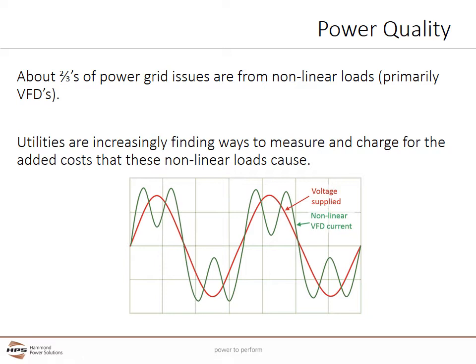Other large non-linear loads can include inductive heaters, arc furnaces, welders, and large DC power supplies and chargers. Non-linear loads now make up a large majority of utility loads. Non-linear loads cause issues for utilities including power quality and higher line losses. Modern utility power meters increasingly allow utilities to monitor the effects of non-linear loads from individual users and charge penalties if a user exceeds harmonic values.